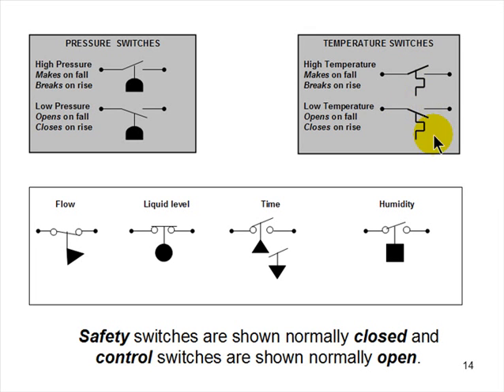This is a cooling thermostat. It's low temperature and it's open, so it's a cooling thermostat. If it was closed in this position, then it would be some kind of probably freeze device or something. It could be a freeze stat. You would put it on a suction line if you were zoning a system and you had a bypass duct. If the small zone is open, that coil is going to get real cold real fast, so you put it on the suction line, it attaches and senses the suction line temperature.